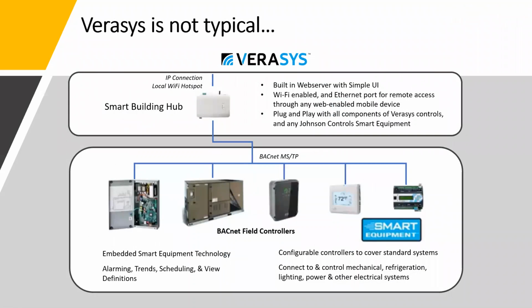So here you have Verasys. As you can see, there is no supervisor, there's no network engine, but like the supervisor controllers, the Smart Building Hub hosts the web server. The difference is that the field controllers used in Verasys are what we call smart equipment. You may see this logo often, and this is really what makes a Verasys system plug and play. The smart equipment holds all of the configuration, data, settings, and intelligence stored within these devices. When one of these smart equipment devices is added to the BACnet MSTP network, it automatically becomes available in the Smart Building Hub. All you have to do is assign it. There's no app to buy, no software subscription licenses, no expensive labor investment. It's just a much lower cost integration.